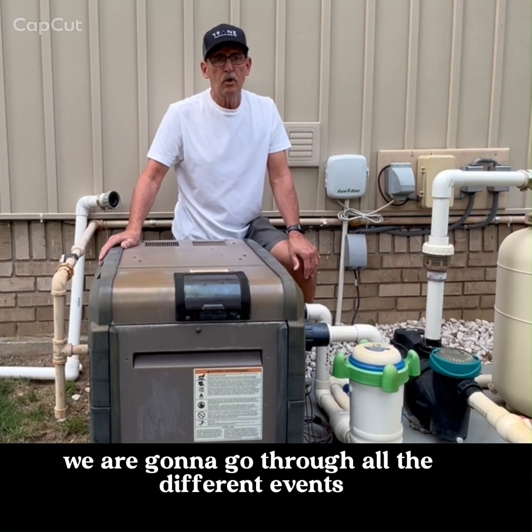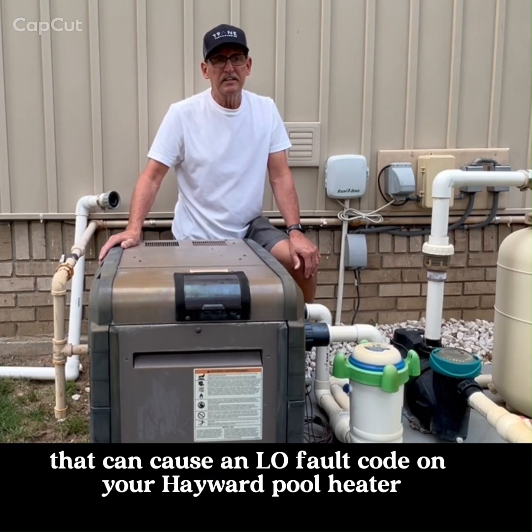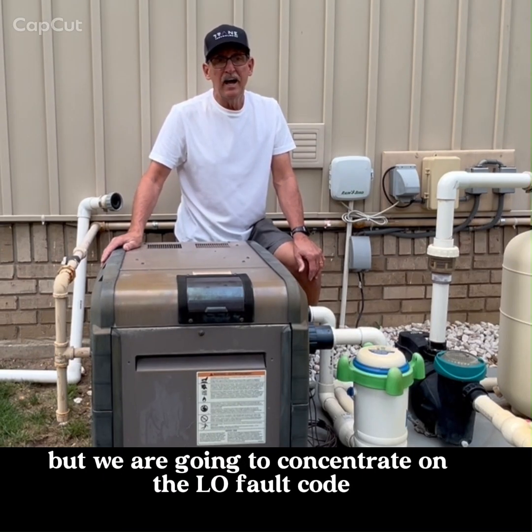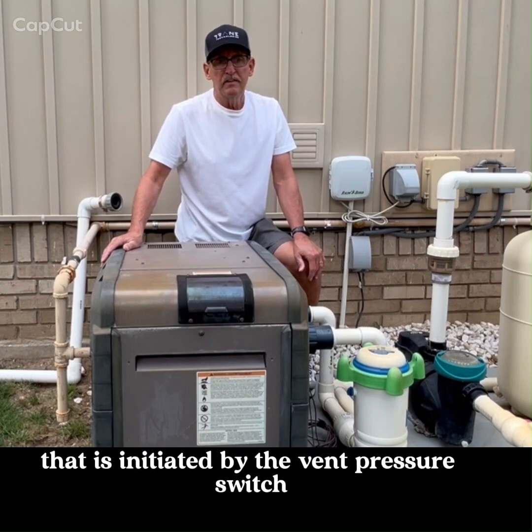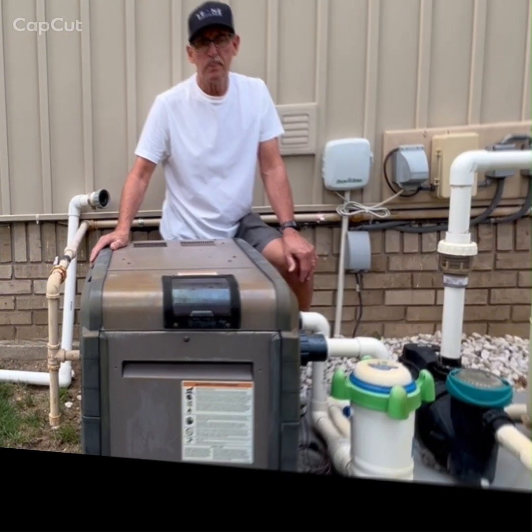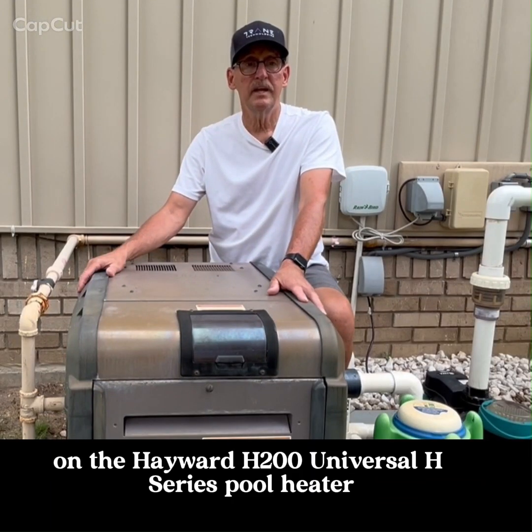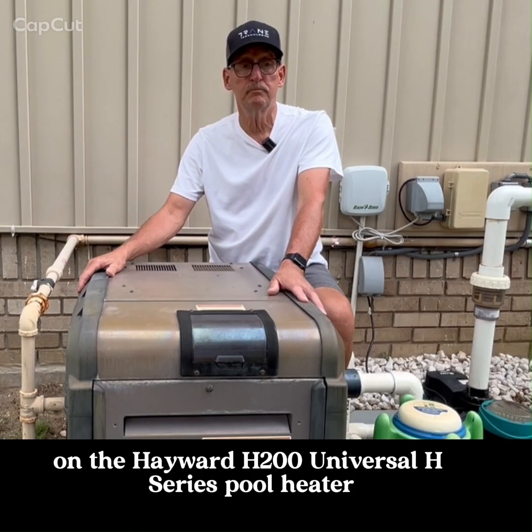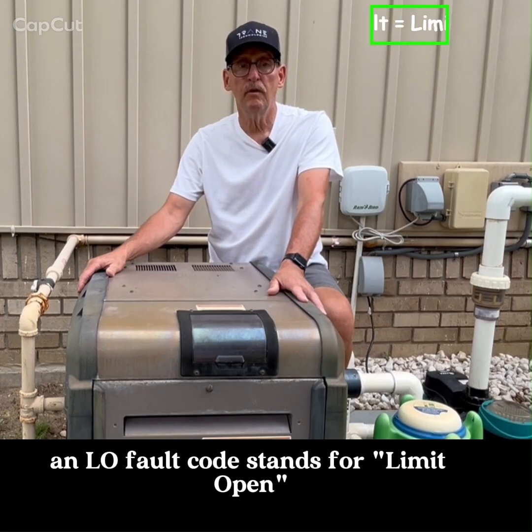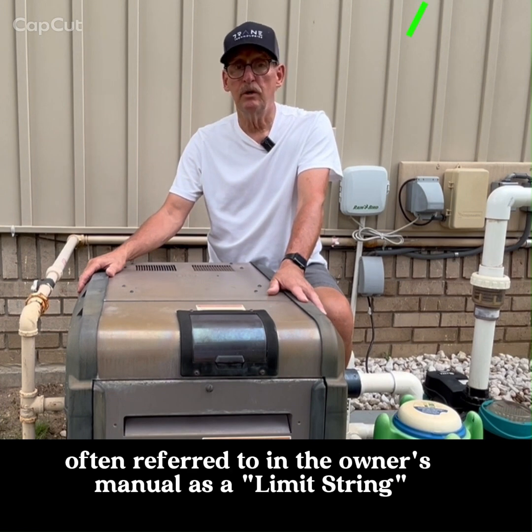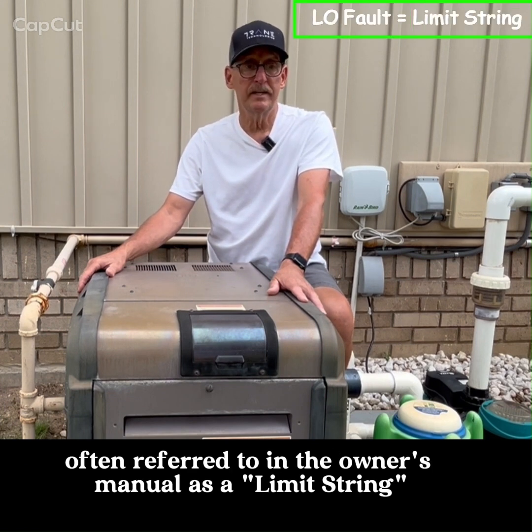Today, we are going to go through all the different events that can cause an LO fault code on your Hayward pool heater. But we are going to concentrate on the LO fault code that is initiated by the vent pressure switch. On the Hayward H200 Universal H Series pool heater, an LO fault code stands for limit open, often referred to in the owner's manual as a limit string.